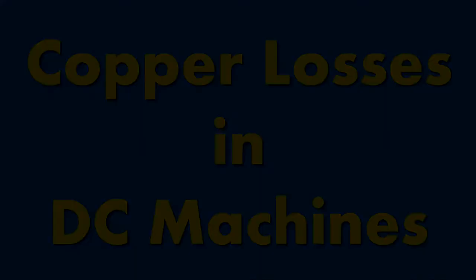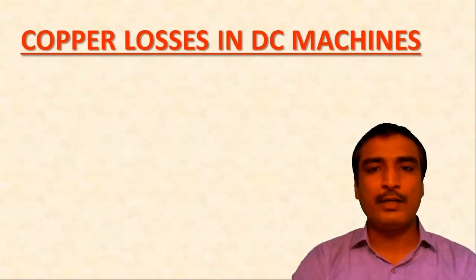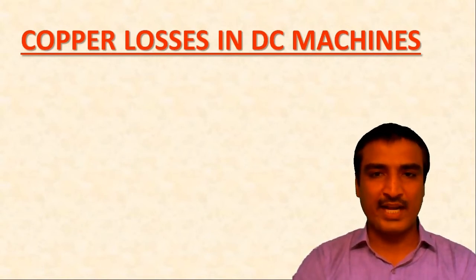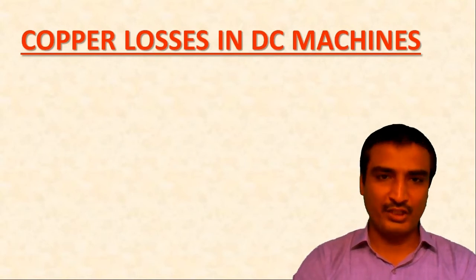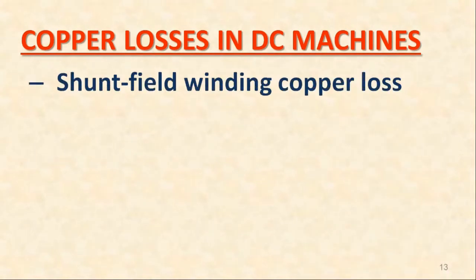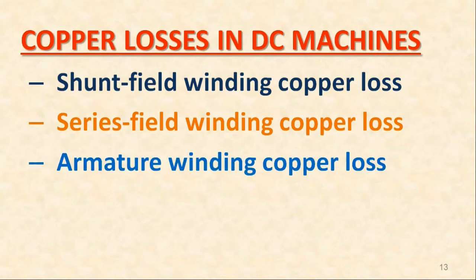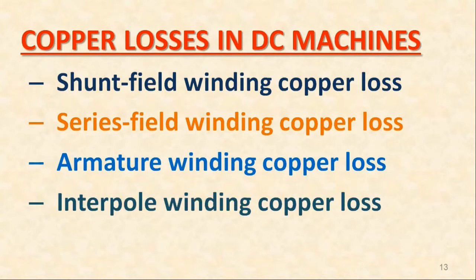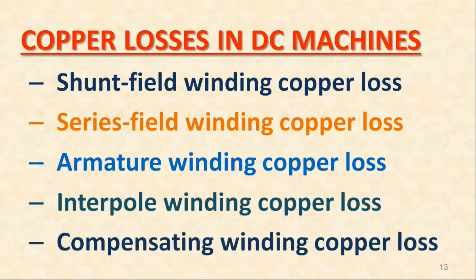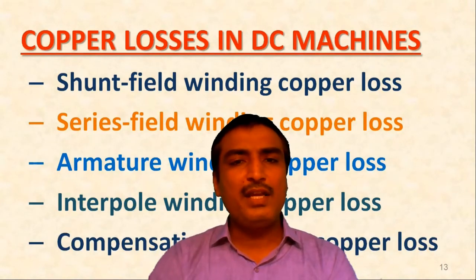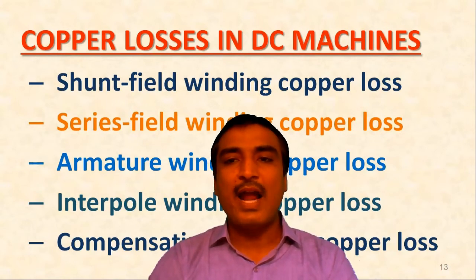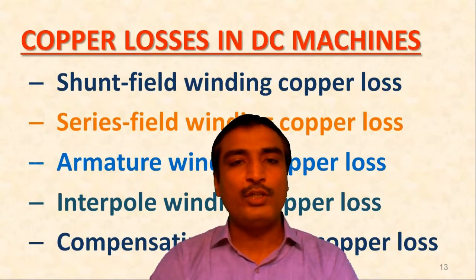Copper losses in the DC machine: The copper losses occur due to the currents flowing through different windings of the DC machine. Hence, the copper losses can be segregated as shunt field winding copper loss, series field winding copper loss, armature winding copper loss, interpole winding copper loss, and compensating winding copper loss. The copper loss in any winding depends on the resistance of the winding and the square of the current flowing through that winding.